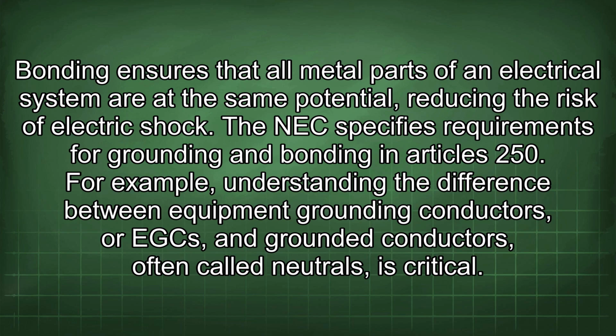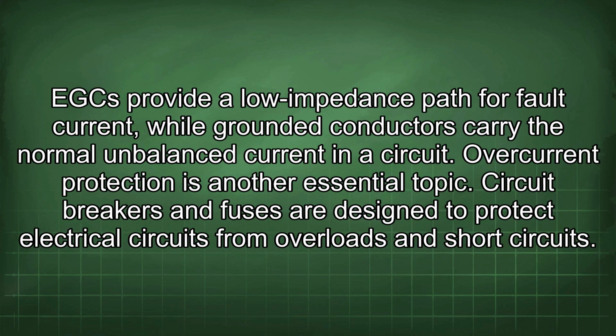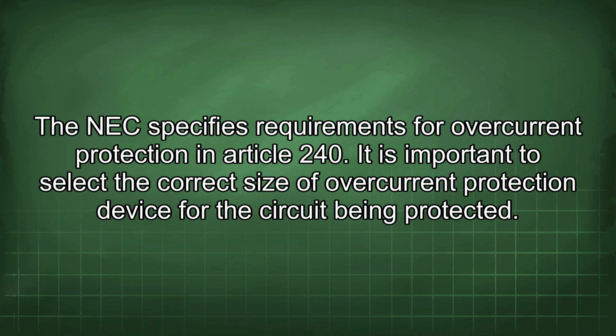For example, understanding the difference between equipment grounding conductors, or EGCs, and grounded conductors, often called neutrals, is critical. Each EGC provides a low impedance path for fault current, while grounded conductors carry the normal unbalanced current in a circuit. Overcurrent protection is another essential topic. Circuit breakers and fuses are designed to protect electrical circuits from overloads and short circuits. The NEC specifies requirements for overcurrent protection in Article 240.